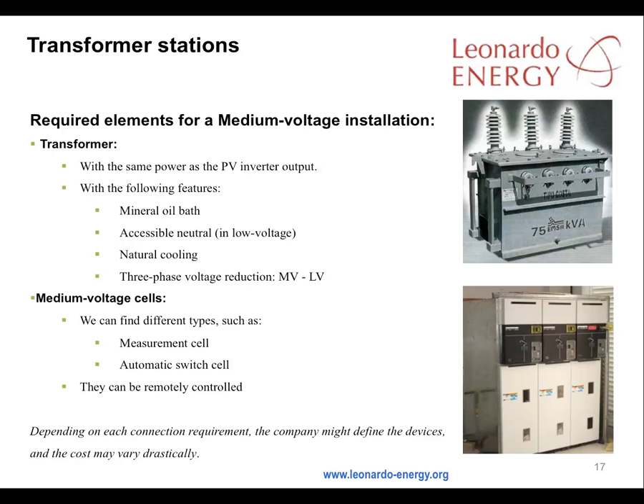A transformer for a medium voltage installation will need to match the output power of the PV inverter. It will require a mineral oil bath and an accessible neutral natural cooling, and three-phase voltage reduction from medium voltage to low voltage. There are different types of medium voltage cells. Measurement cells and automatic switch cells can be controlled remotely. Needs may differ according to the connection requirement and as a result costs may vary dramatically.